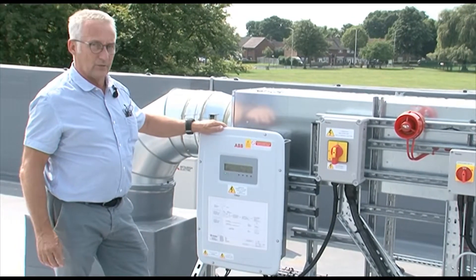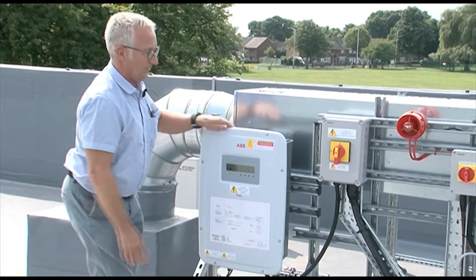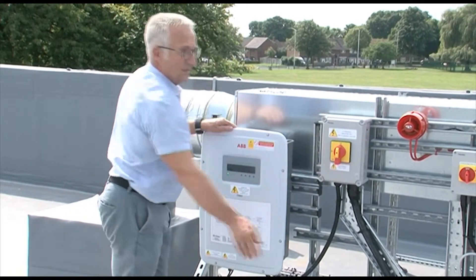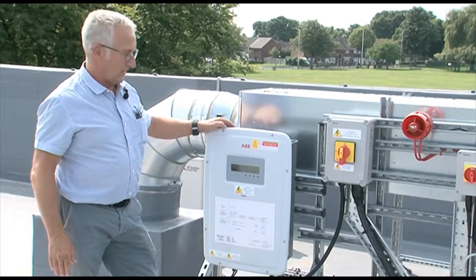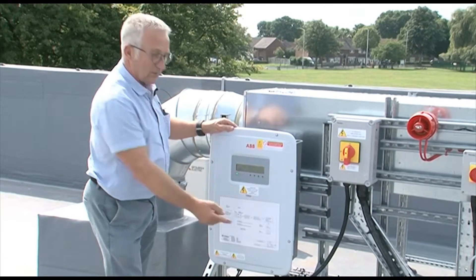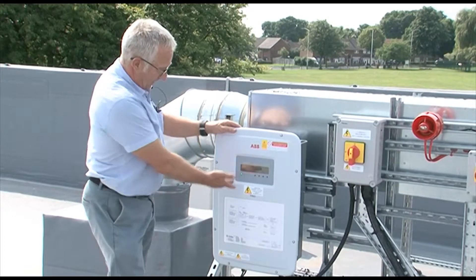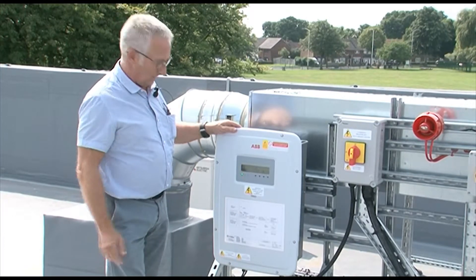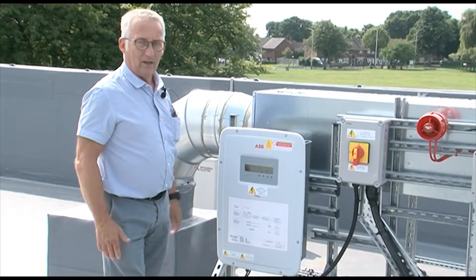To turn back on again, it is all in reverse: operate the DC switch under the inverter, then the AC switch here, then switch on the AC switch down at the MCCB board downstairs. Your inverter display is here and is duplicated by the side of the LV panel downstairs as well. A green light shows power — everything is good. An amber light shows alarm and fault.